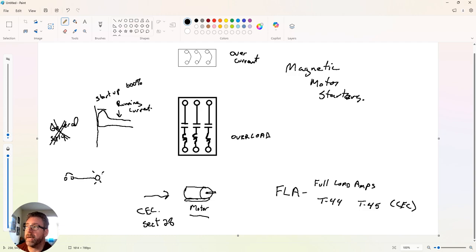The process is we take our load, find out what the wire size is, the AWG size, and then figure out what the breaker size is using table 13. So we're making sure this breaker is protecting everything down line of it: the load, and also the conductors.